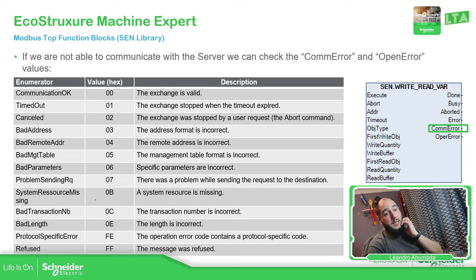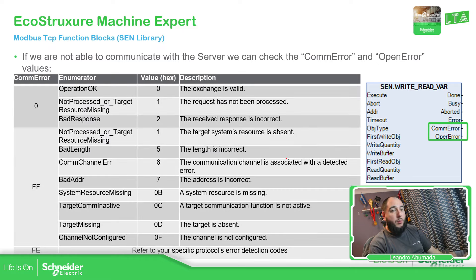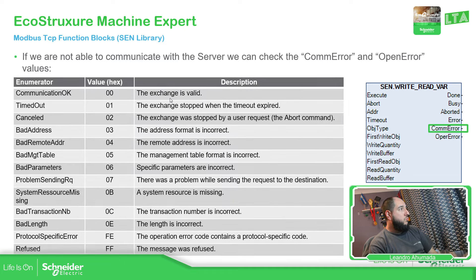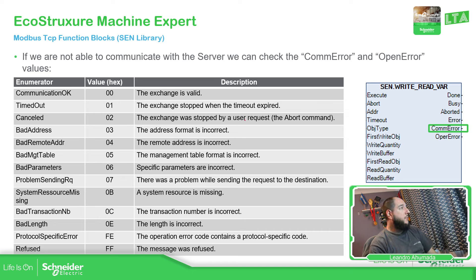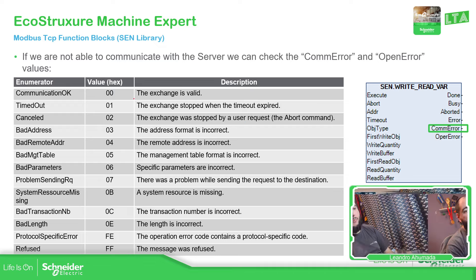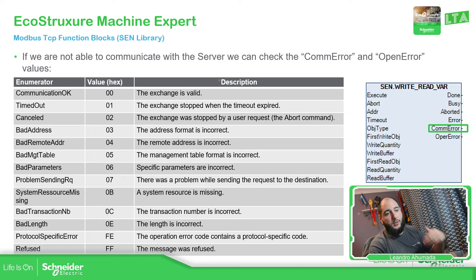The OPER error is taken from the Online Help and gives you full detail about what happened. Depending on the COM error, you can check the operational error. For example, if the address format is incorrect or the message is refused, depending on what the problem is with the communication, you should be able to see it. Regarding timeout, if it's zero, you just wait indefinitely. Otherwise, you can define the timeout.